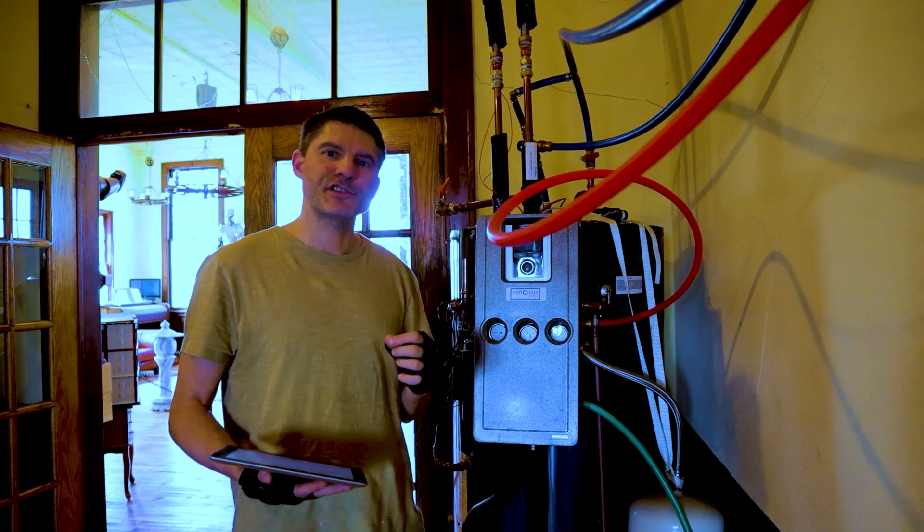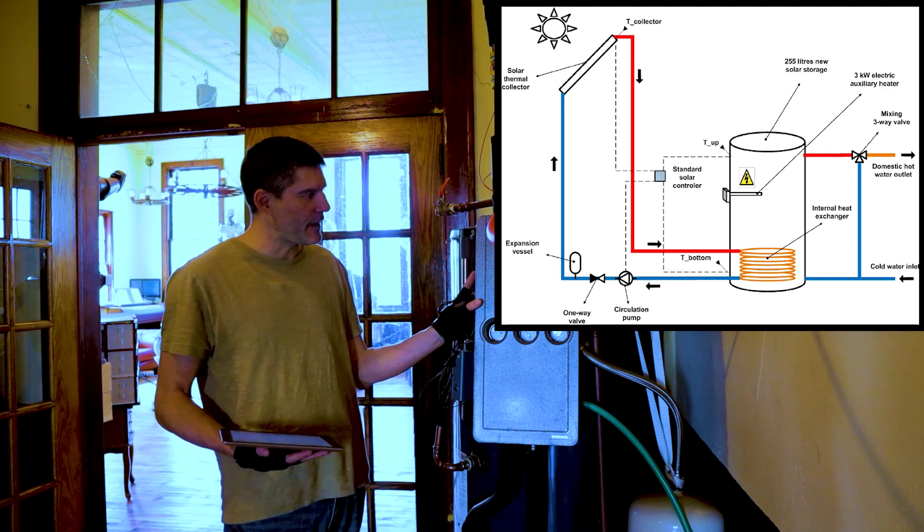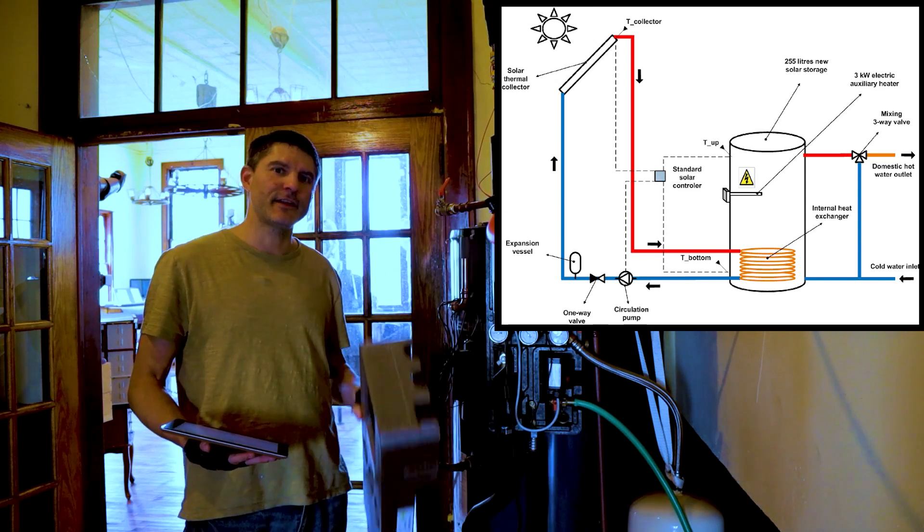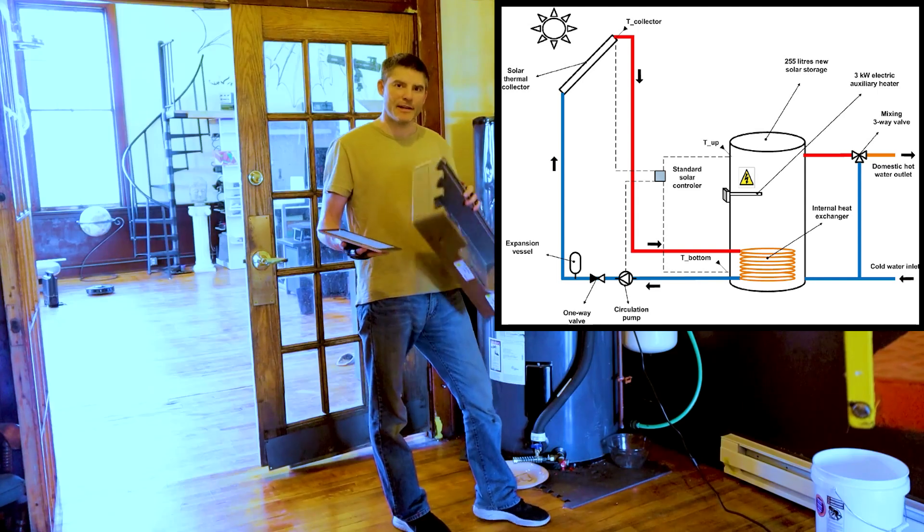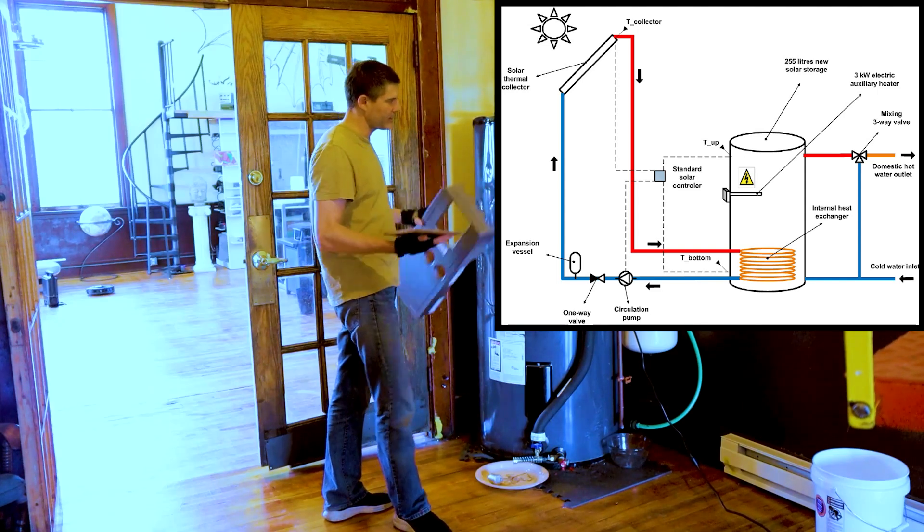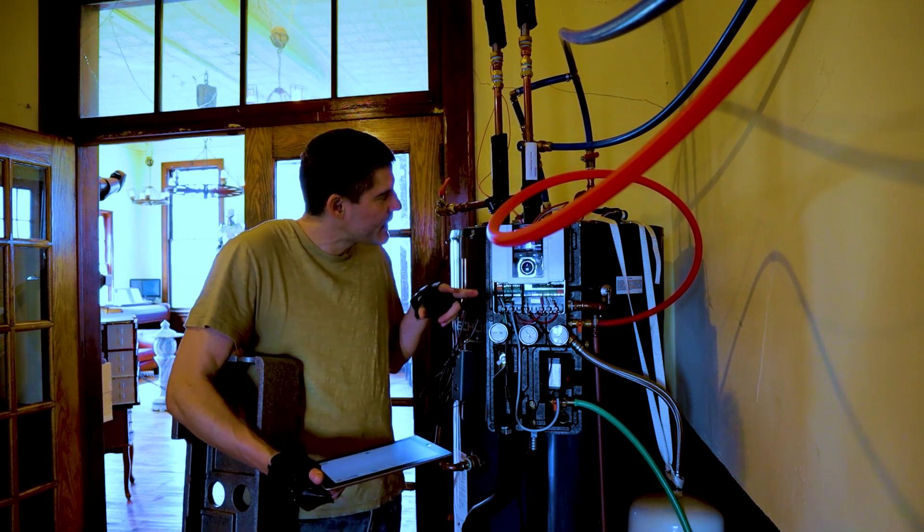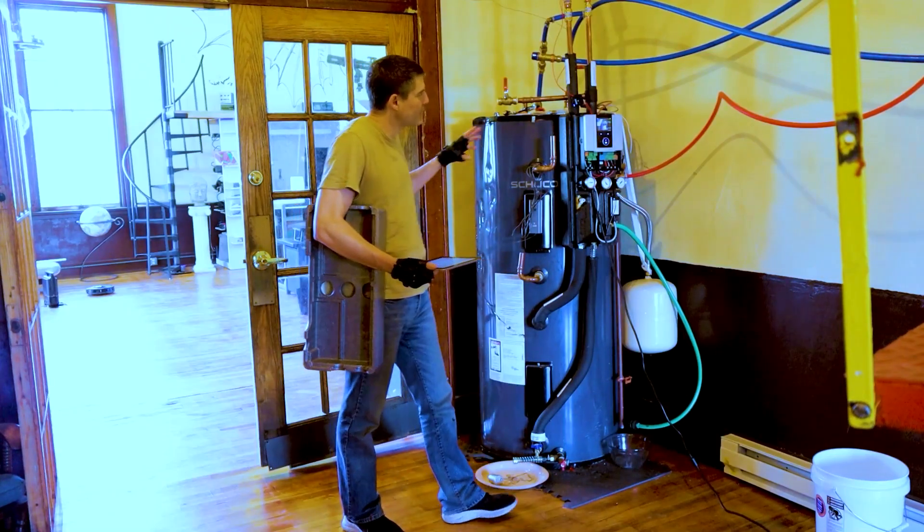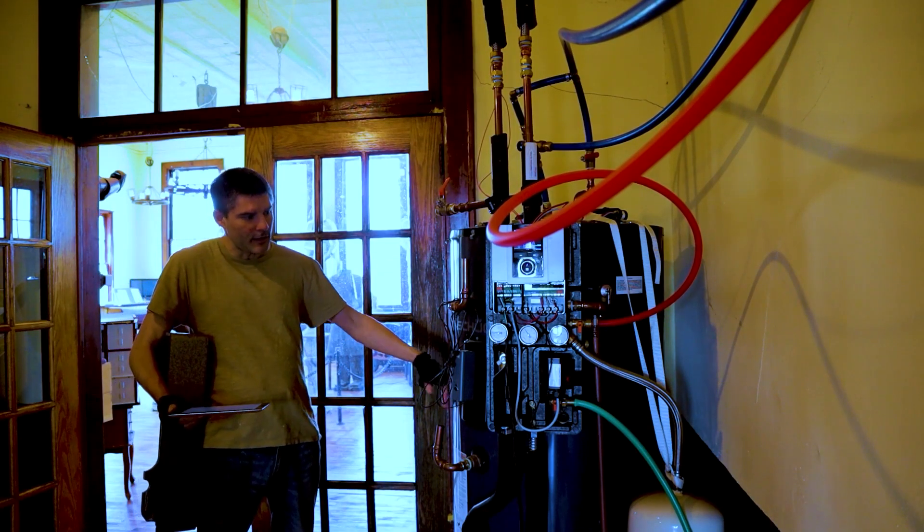The system has temperature sensors up on the roof and inside the hot water tank and when it senses that the temperature is greater outside than it is inside, it'll turn on the circulating pumps and then heat the water inside the water tank. So our little computer right now tells us that outside the temperature is 189 degrees Fahrenheit and about 65 degrees inside.